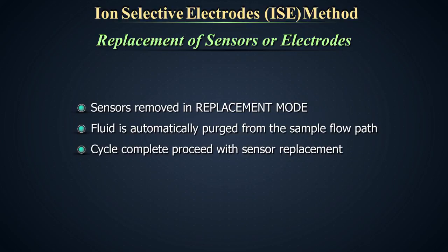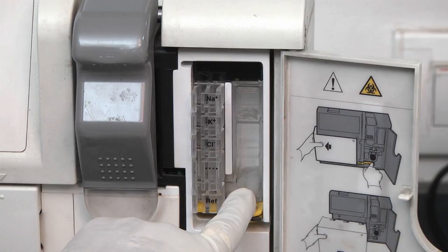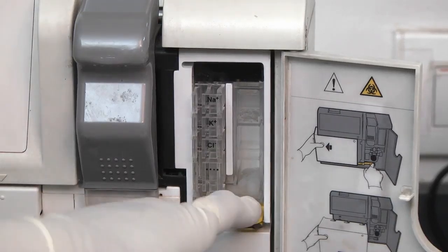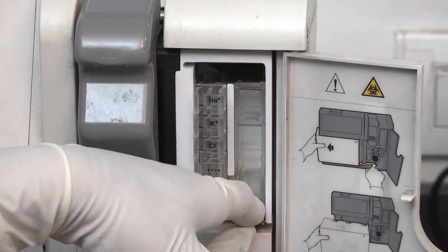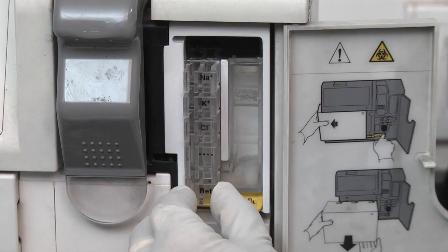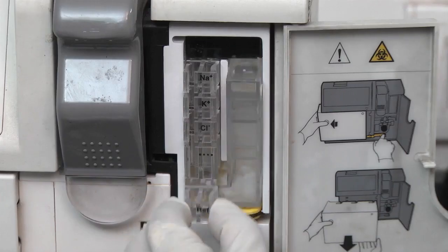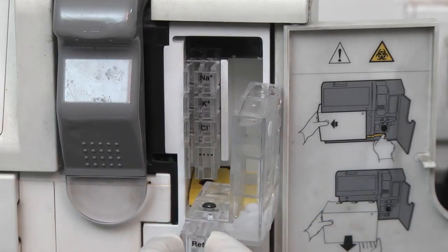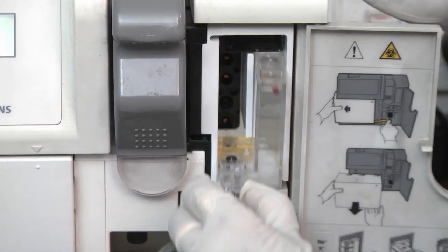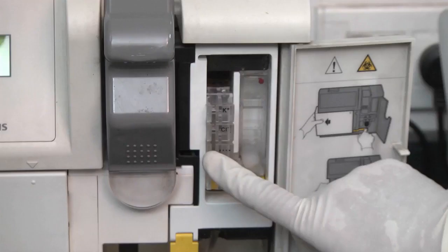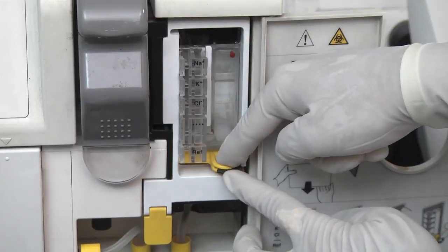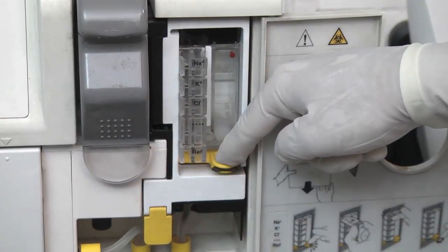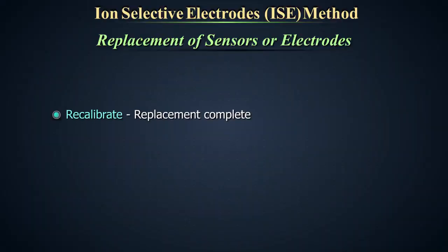When the purge cycle is complete, proceed with sensor replacement. To remove a sensor, push the compression plate down until the latch locks into the open position. Grip the desired sensor handle, squeeze and pull it straight out from the sensor module. To install a new sensor, push the sensor gently into its designated slot till the handle snaps into the sensor module. Do not force. Recalibrate when replacement is complete.